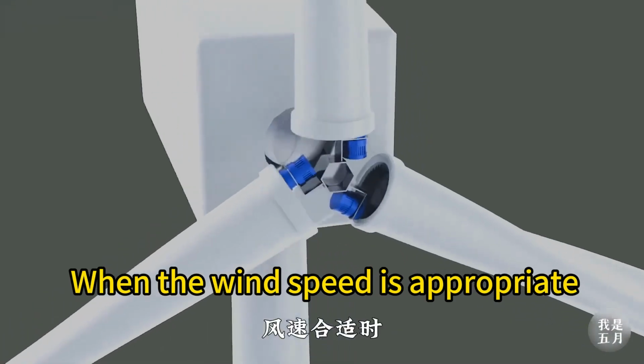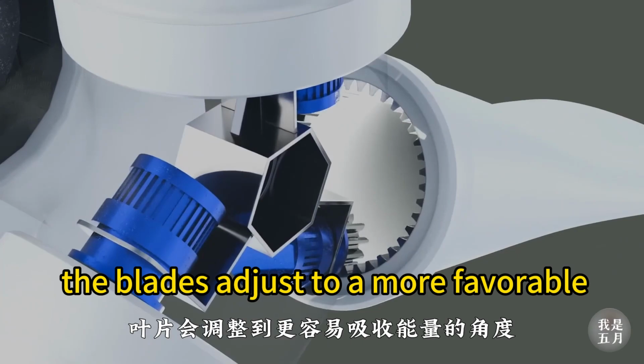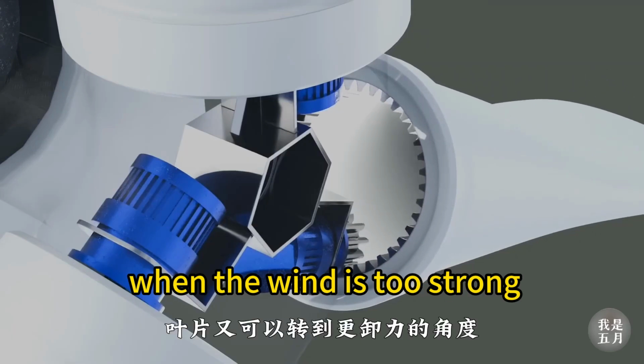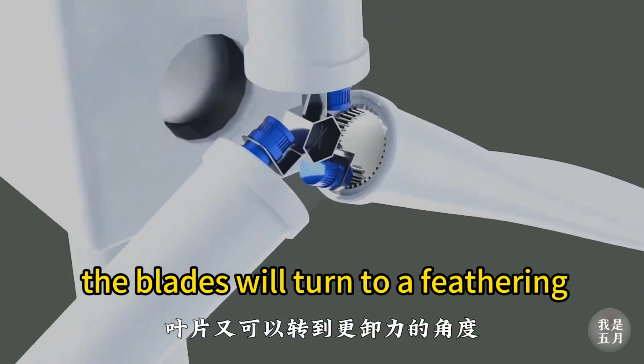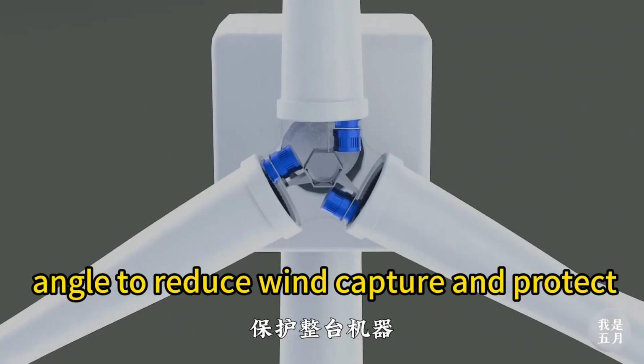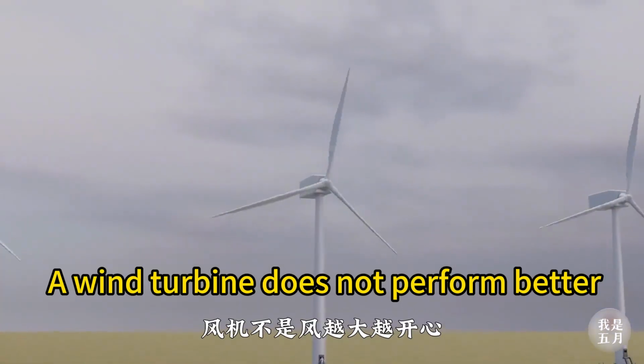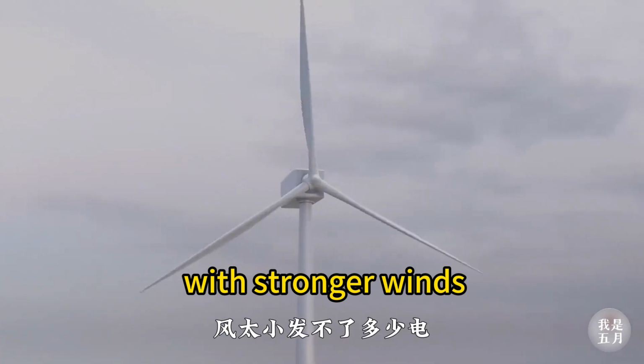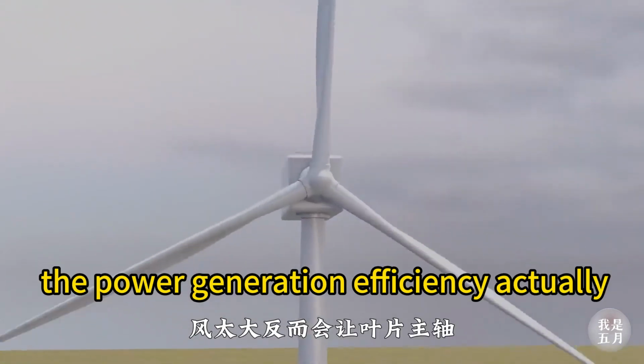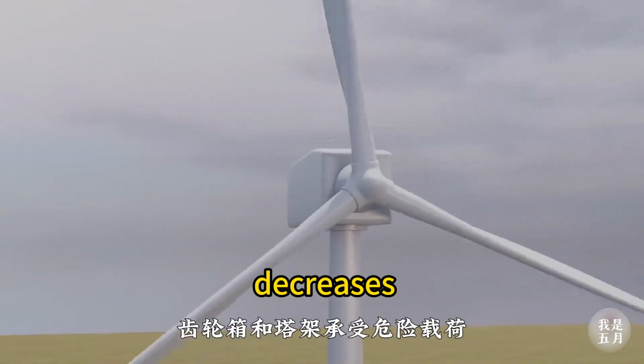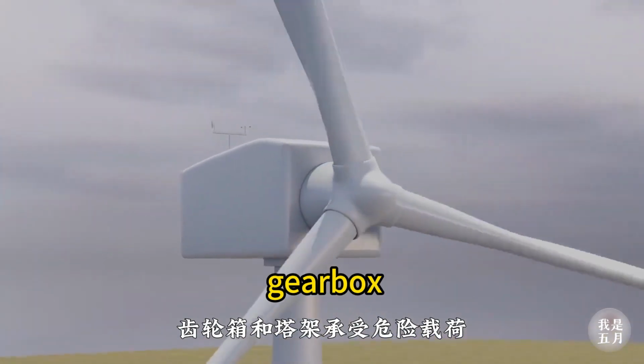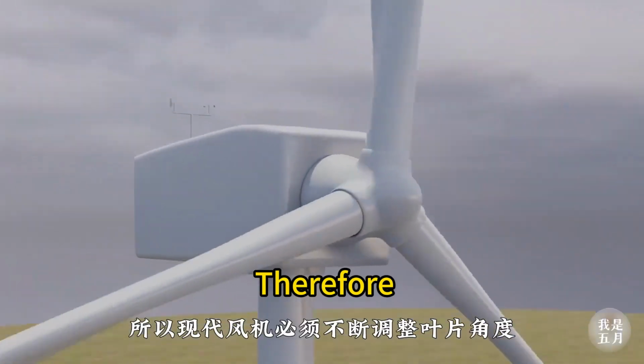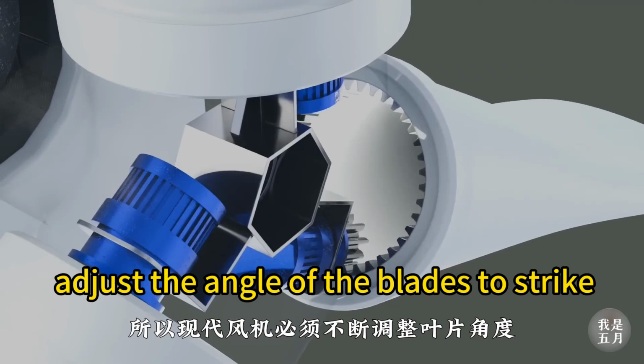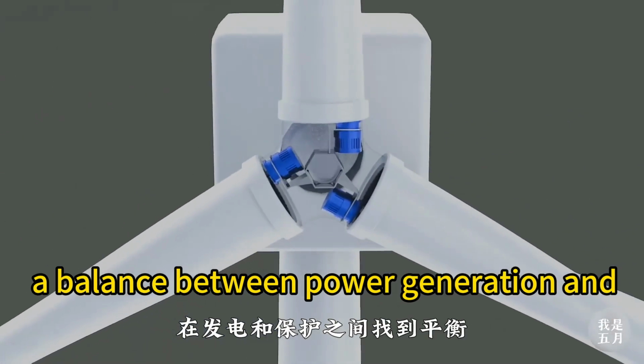When the wind speed is appropriate, the blades adjust to a more favorable angle for energy absorption. When the wind is too strong, the blades will turn to a feathering angle to reduce wind capture and protect the entire system, which is crucial. A wind turbine does not perform better with stronger winds. When the wind is too strong, the power generation efficiency actually decreases, which may put the blades, main shaft, gearbox, and tower under dangerous loads.